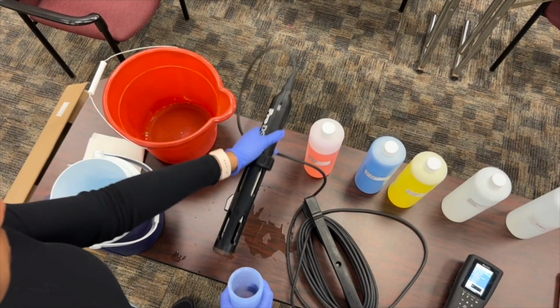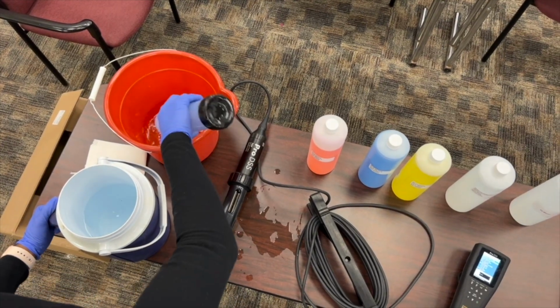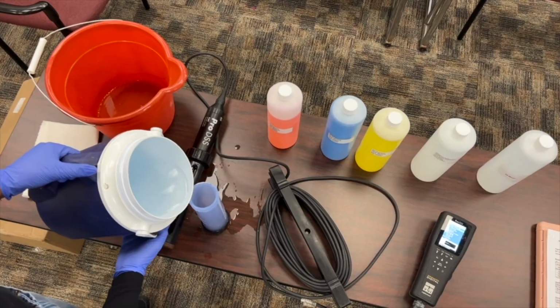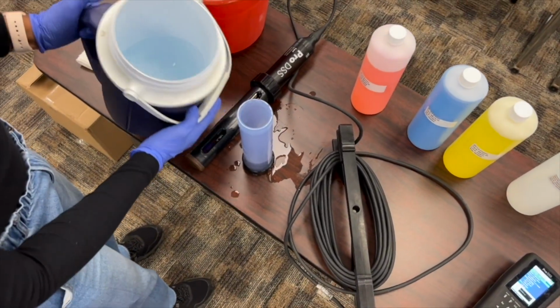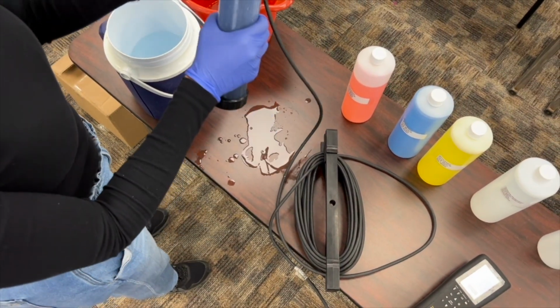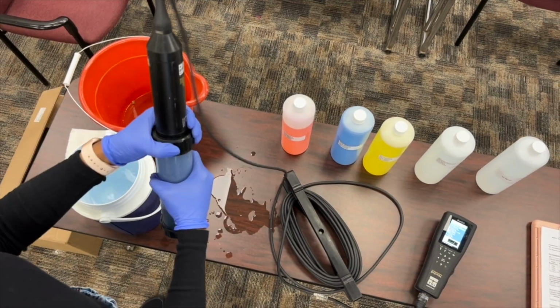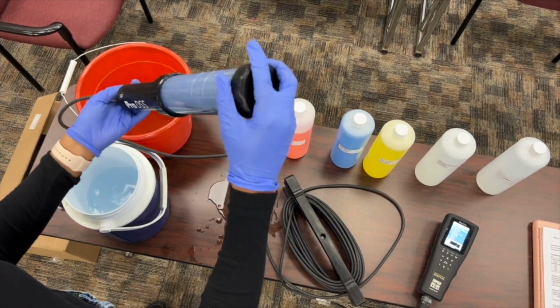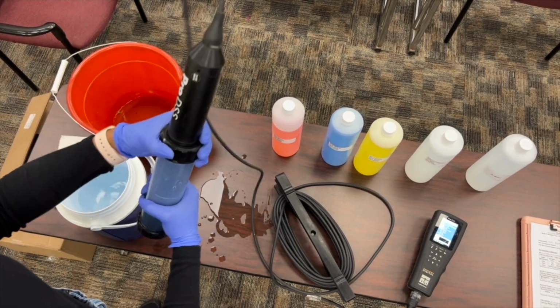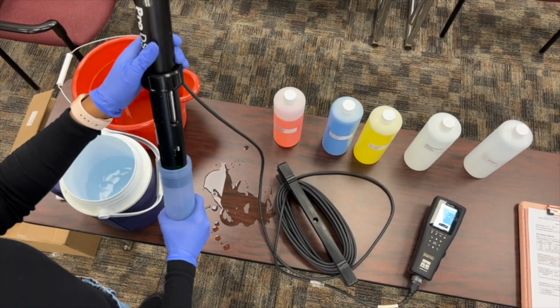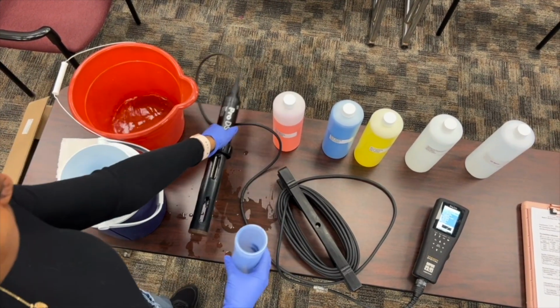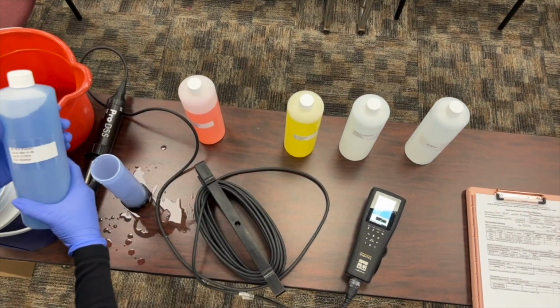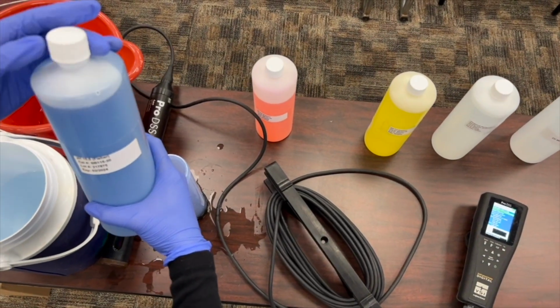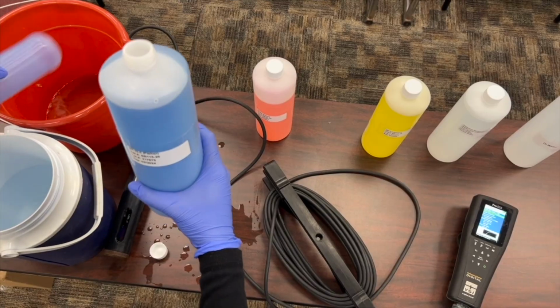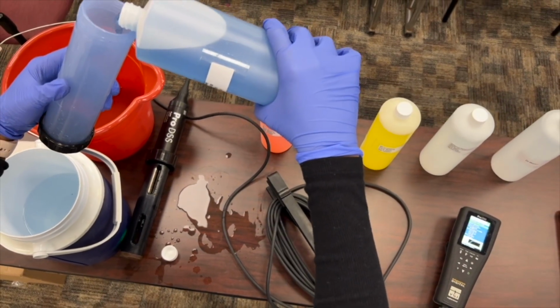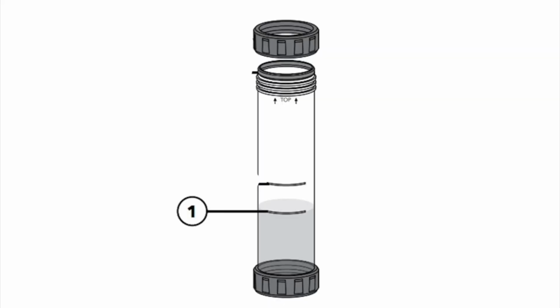Now, you can calibrate for pH 10.00 or basic conditions using the blue buffer. Begin by discarding the red buffer we used for pH 4.00. Then rinse the calibration cup and sensors with fresh water. Once you're ready, use the pH 10.00 buffer to fill the calibration cup to the first line and insert the sonde.